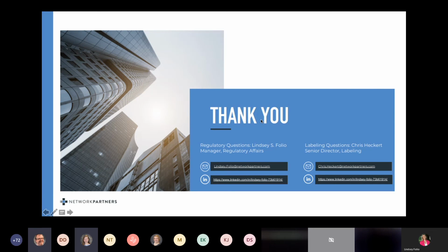Thank you for that. Next up, please explain how the BUDI is used. Okay, so by that, I'm assuming you mean the Basic UDI device identifier. There are a few areas like I covered where it will be used, and the one most applicable to this topic is on the labeling. So it's included on the product label and any higher levels of packaging. And then it'll also be required to be entered in EUDAMED once that's up and running.